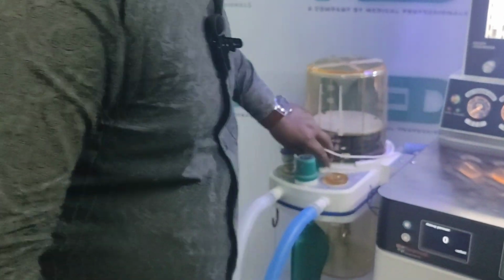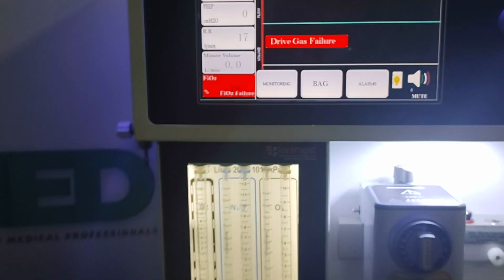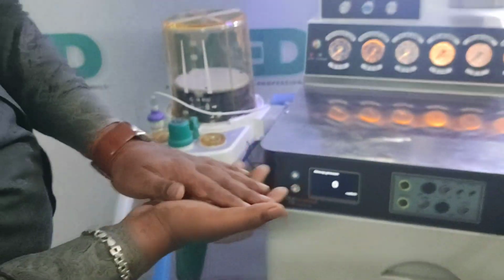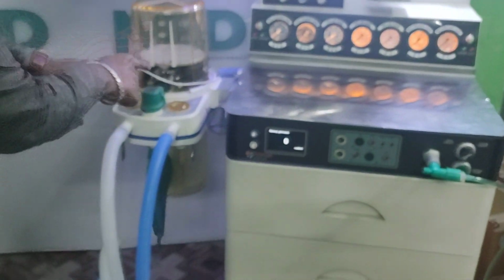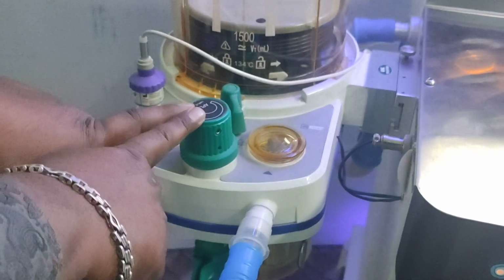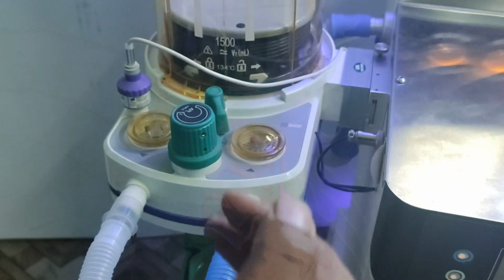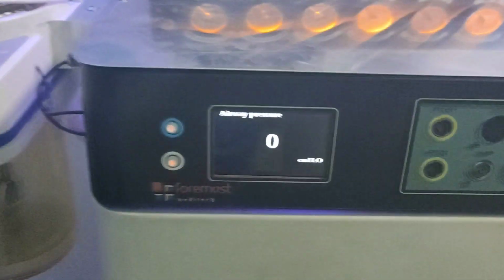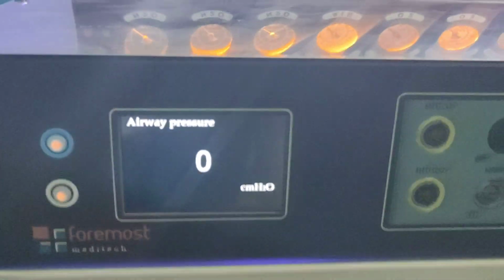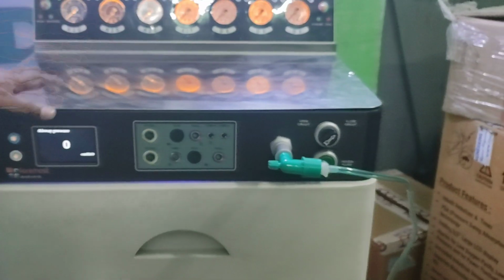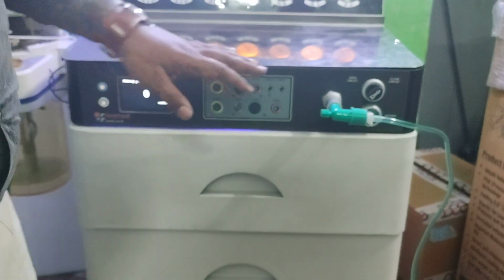When you are using manual mode, using the bag in manual mode, you press from here to understand the highest pressure going to the patient when you apply the APL valve. But you have to make sure of the pressure. If you want to check it, here is the display. You can see the airway pressure being delivered to the patient. So you will be highly sure about the air delivery.